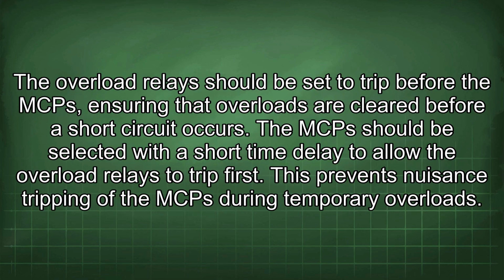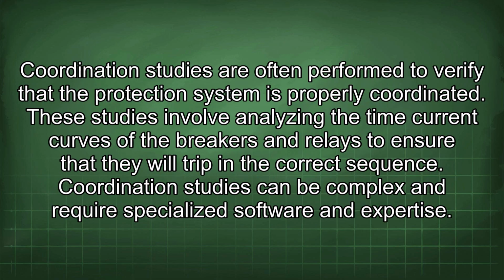The overload relays should be set to trip before the MCP, ensuring that overloads are cleared before a short circuit occurs. The MCP should be selected with a short time delay to allow the overload relays to trip first. This prevents nuisance tripping of the MCP during temporary overloads. Coordination studies are often performed to verify that the protection system is properly coordinated. These studies involve analyzing the time current curves of the breakers and relays to ensure that they will trip in the correct sequence. Coordination studies can be complex and require specialized software and expertise.